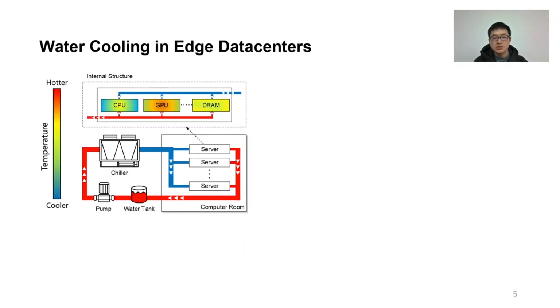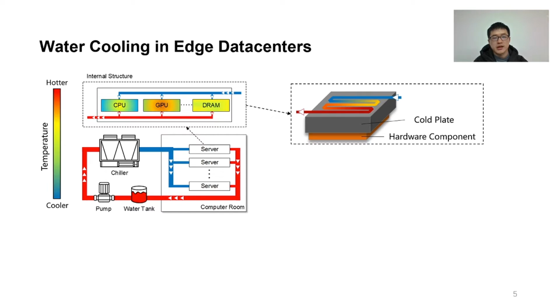In a conventional coarse grained water cooling system, all the servers and internal components share the same water temperature and flow rate. Each component is directly attached to a cold plate and disperses the heat to the internal cooling water. After absorbing heat from different hardware components, the water gathers together and then is cooled to some temperature by the chiller. For the safety of all hardware components, this temperature is usually set to be low enough so as to cool down some high utilization hardware components with a high temperature. However, since other low utilization hardware components are overcooled, this wastes a huge amount of cooling energy.